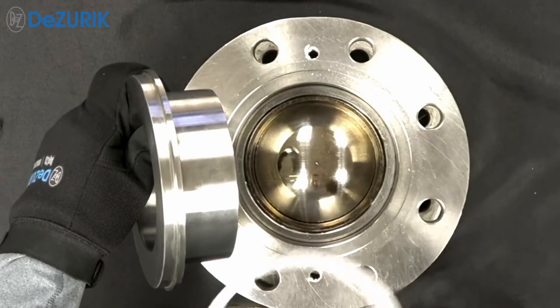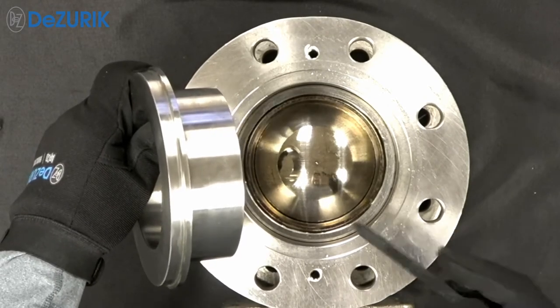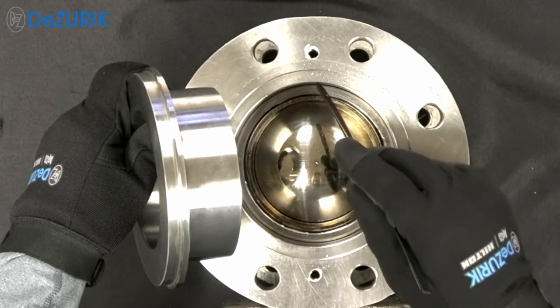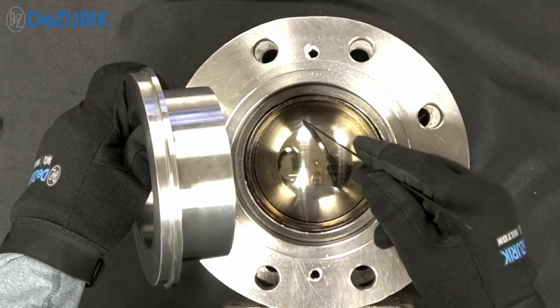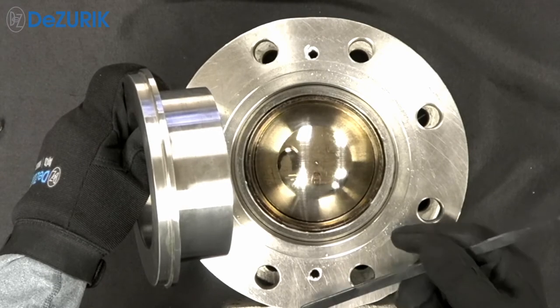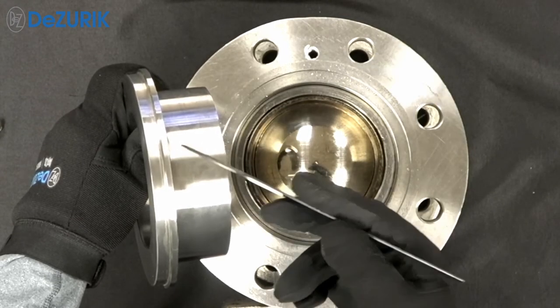DeZurik's V-Port ball valve seat retainer does not have any threaded components that are exposed to the process media. The internal trim does not need to be removed to replace the seat, and no special tools are required. The loading of the seat against the ball is controlled by the dimensions of the seat retainer and valve body cavity.